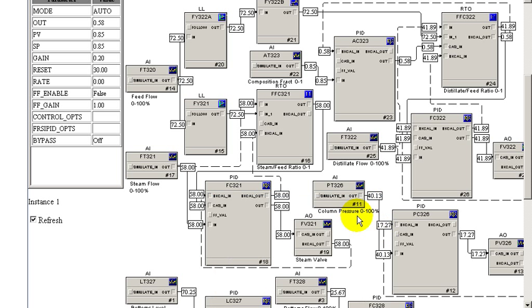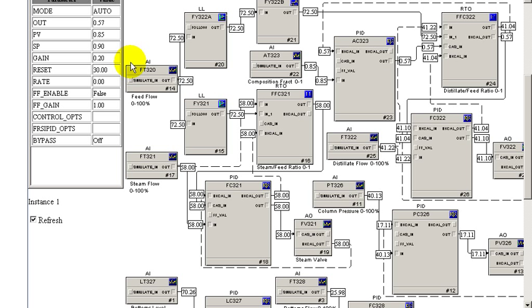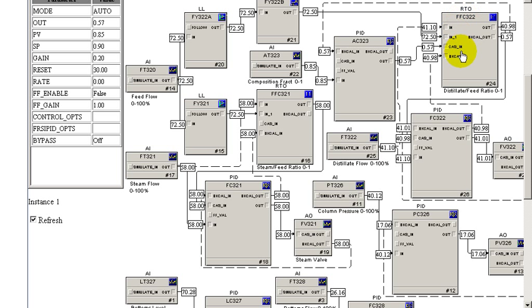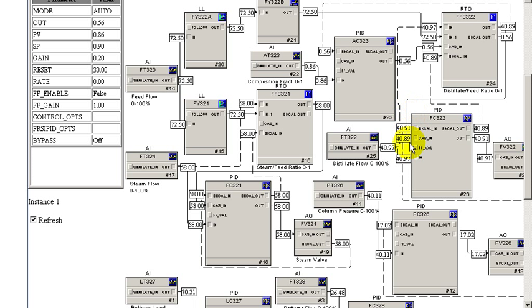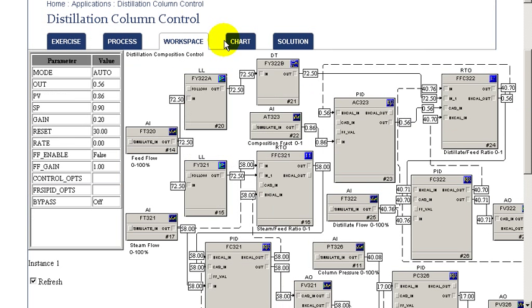We're going to go from 0.85 up to 0.9 in terms of its concentration. As a result, the controller is going to adjust the ratio of the distillate to feed to drive the composition higher in terms of the light component. We're actually going to cut down on the distillate flow rate.